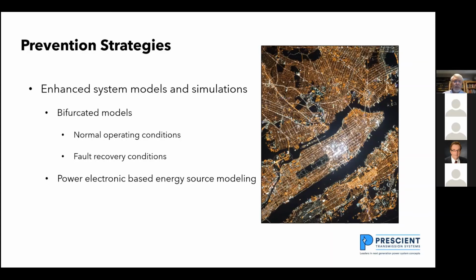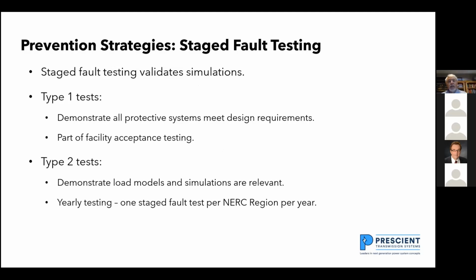The strategies I need to stop wide area blackouts: I need enhanced system models and simulations. I need bifurcated models, and the bifurcated models have to look at fault recovery conditions, and they have to include power electronic based energy source modeling. I also need to do staged fault testing. I've been in the industry for 50 years, and it's been 40 years since I participated in a staged fault test.